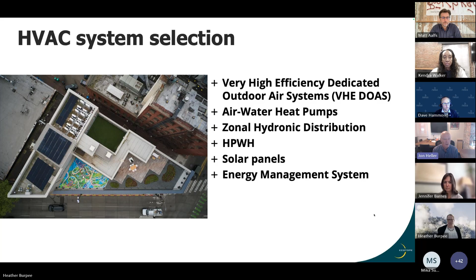So the heart of the design is really these high efficiency heat recovery ventilators. They're the only pieces of equipment that need to run during most occupied hours of the building to provide fresh air and exhaust air. They're counterflow heat exchangers to provide a very high level of thermal effectiveness so that no tempering of the air is required. The 100% outside air can be delivered directly to the occupied spaces. And since it's 100% outside air that's sized just for air quality, the ducts are as small as possible, which is important in a historic building like this. And then air quality monitoring and variable speed, high efficiency fans with zonal controls means that the fan energy is as small as possible as well.